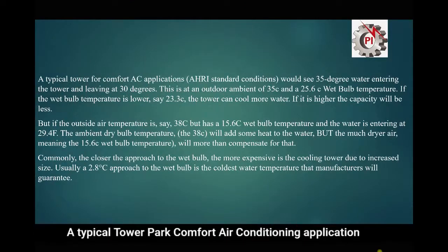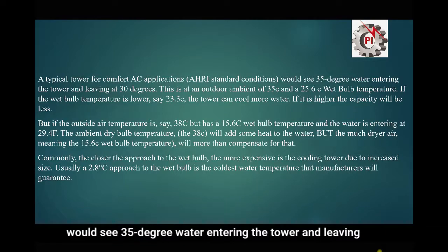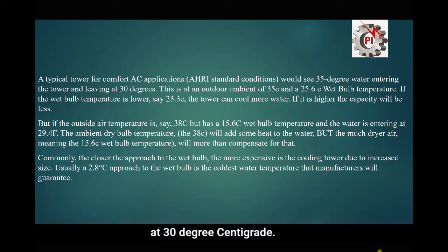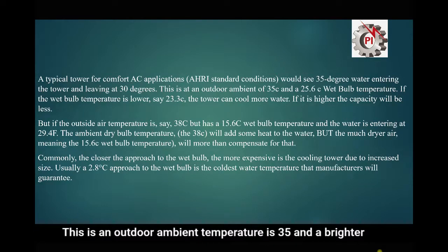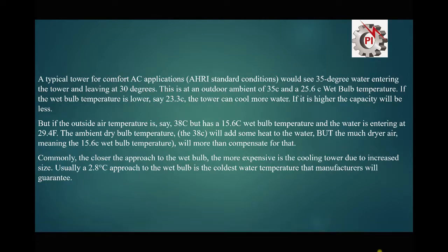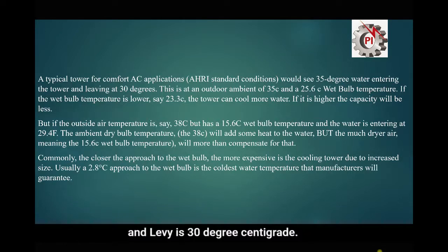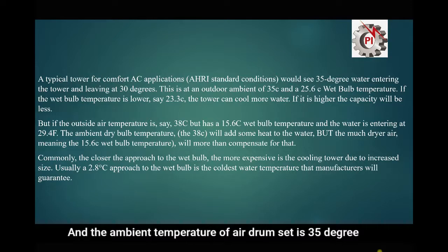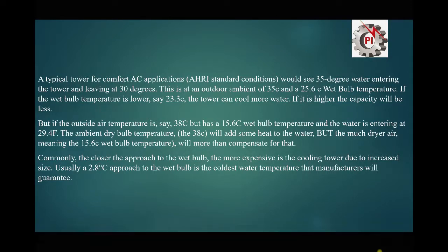A typical tower for comfort air conditioning applications under ASHRAE standard conditions would have water entering the tower at 35°C and leaving at 30°C, with an outdoor ambient temperature of 35°C and a wet bulb temperature of 25.6°C. In this case, if the wet bulb temperature is lowered — say to 23.3°C — the tower can cool more water.